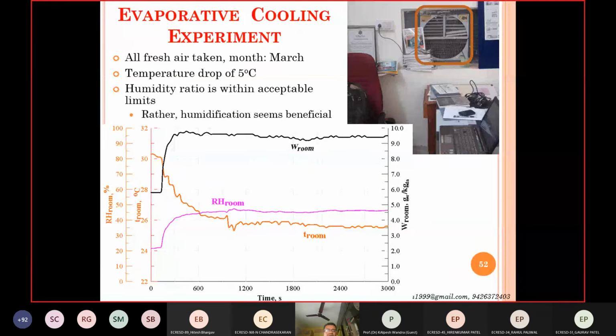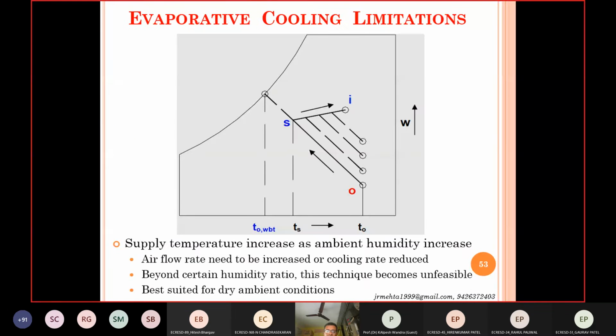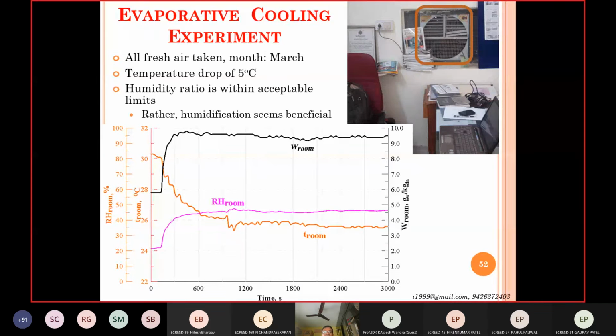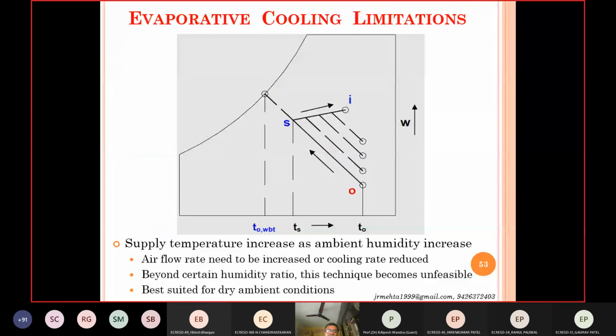I had earlier done some experiments in my lab, and this showed that in the month of March and the earlier part of April, using a desert cooler in Vadodara is a good idea. It provides you the comfort conditions. But if you go up to the end of April and May, and not in June, you should not be using it. You cannot use a desert cooler for comfort cooling when the ambient humidity is already high. So it depends upon the weather conditions and the climate whether to go for evaporative cooling or not. When the ambient is dry and hot or warm, evaporative cooling could be a good choice.